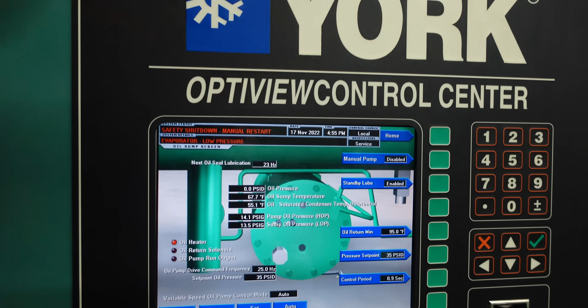Well, during that time, if that bracket was already weak and had a hairline fracture, that pump generates enough vibration—especially if it was an older pump, maybe having some kind of minor bearing issue—that the vibration alone could have been enough to finish the stress fracture off and drop all the weight, which would explain how we go from everything working fine, no leak when I was here last, to now all of a sudden having this leak as a big problem.